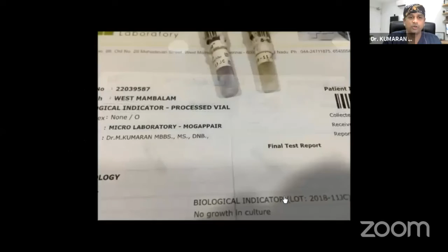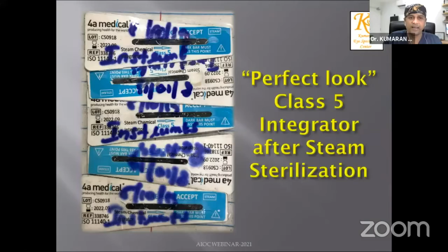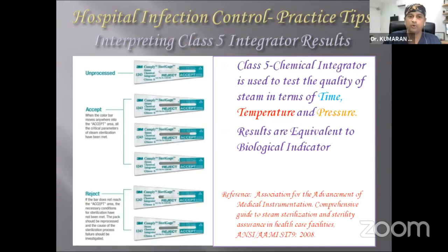There are separate biological indicators for ETO and steam sterilization. Before you introduce a new autoclave into installation, make sure that you have 2 biological indicators which have to be negative before you start using your autoclave. A class 5 autoclave indicator is equivalent to a biological indicator, and this is a perfect look of a biological indicator. These are the manufacturer guidelines which show what is negative and what is positive for a biological indicator. Please follow this and make sure that you read it every time before you start your surgery.